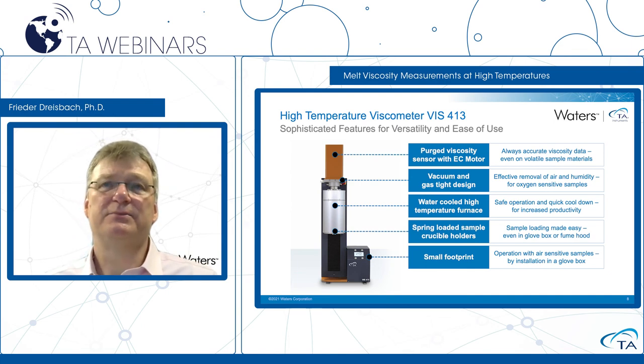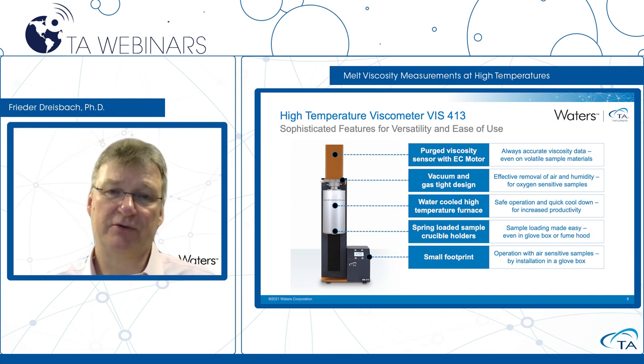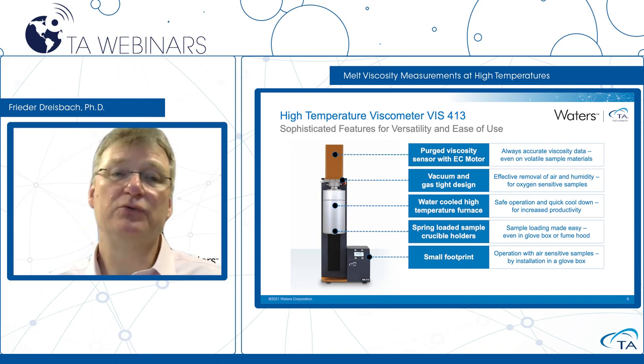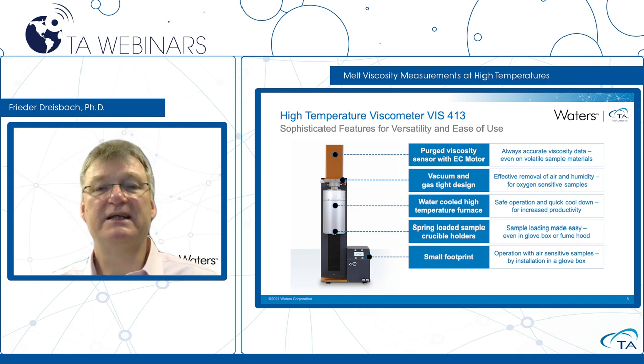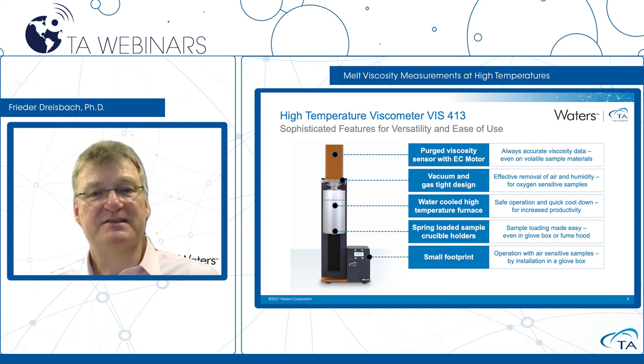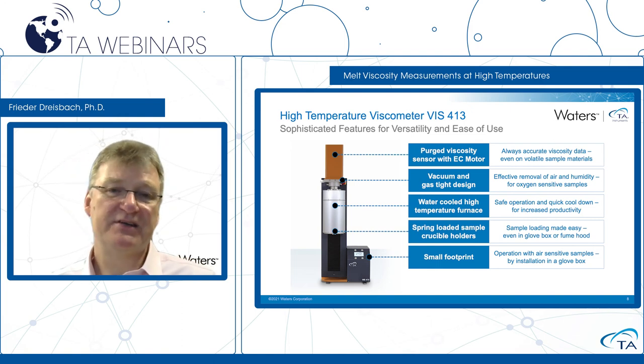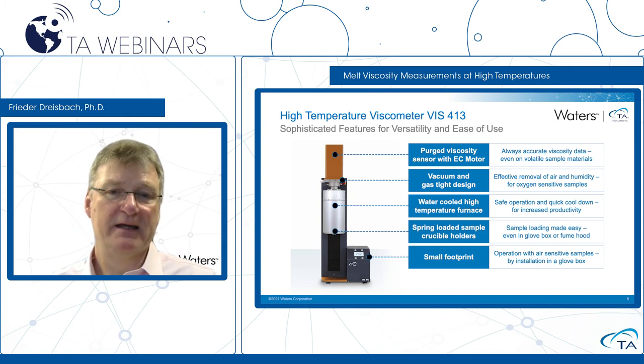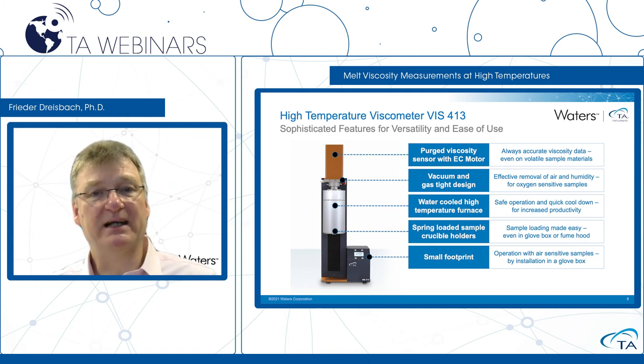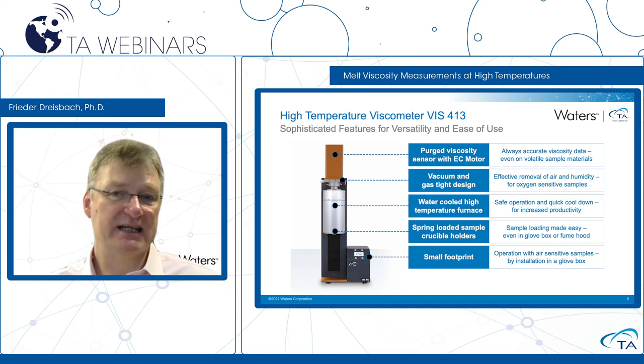Going into more specific parts of the instrument: we have a viscosity sensor on top — the EC motor. A special feature built into the new viscometer is that this part of the instrument can be purged. In a viscometer, the sample is heated to high temperature, and some sample materials have volatile components that evaporate during heating. What we want to avoid with this purge of the sensor area is that vapor goes up into our viscosity sensor and deposits — for instance on the optical encoder or parts of the EC motor — causing contamination in the sensor area.